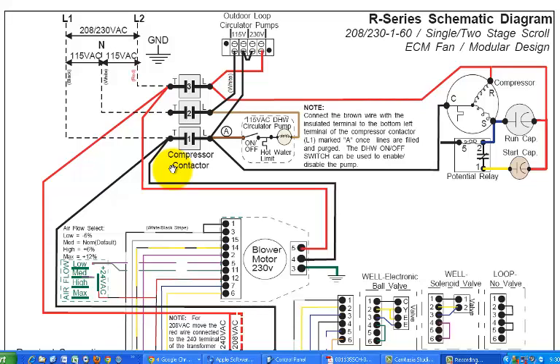And another term for it, by the way, that you might be more familiar with is a relay. And it's a magnetic switch. And in this particular case, what we've actually got, to fall back into some electrical jargon a little bit, is a triple pole single throw switch. Now what that really means is that if we look at this, there is a switch there, another switch there, and again a separate switch there, hence the triple pole. And each one of those is going to be somewhat independent from the other, but they are all going to act simultaneously. And the fact that we call it a single throw switch means that it is either off or on.